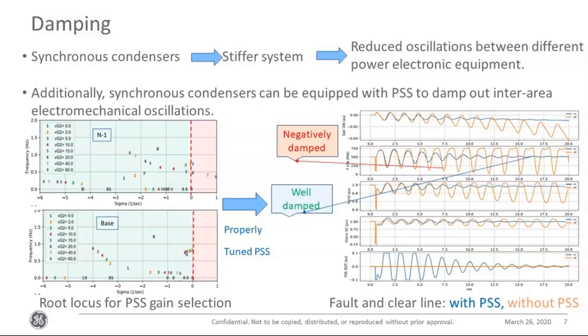And as you increase the gain beyond 10, that causes the mode to swing back and go further to a poorly damped state. And you can see that the gains of 6, 7, 8, that's gains of 20, 40, and 60, are clearly unstable. They are negatively damped. So for this particular project, with the objective of getting sufficient damping for this inter-area mode and also maintaining sufficient gain margin, we went with a gain of 5.